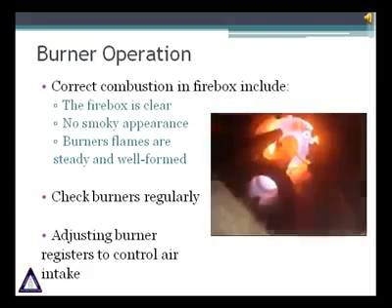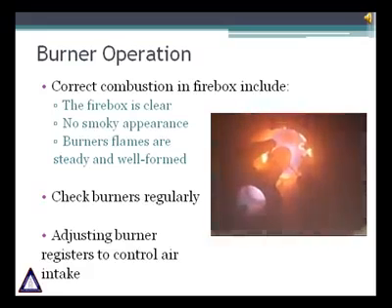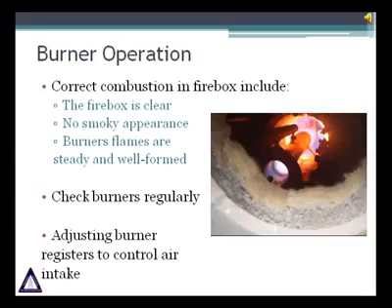It is highly recommended to check burners regularly for any signs of blockage or unusual flame conditions. If the burner flames are long and lazy, it is a sign of poor mixing. Increasing the airflow to the burner can reduce flame length. It is also necessary to control the air intake. Excess oxygen control is normally done through burner register in all natural draft heaters. In balanced draft heaters, FD fan dampers control the air supply.